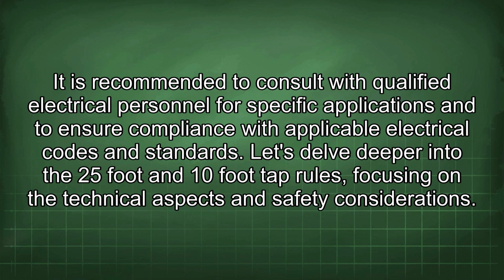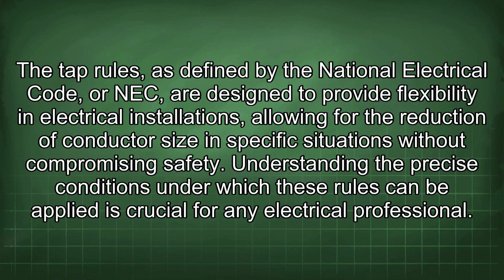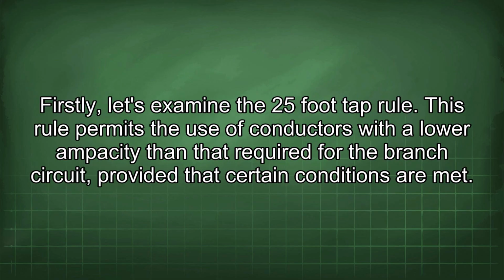Let's delve deeper into the 25-foot and 10-foot tap rules, focusing on the technical aspects and safety considerations. The tap rules, as defined by the National Electrical Code, or NEC, are designed to provide flexibility in electrical installations, allowing for the reduction of conductor size in specific situations without compromising safety. Understanding the precise conditions under which these rules can be applied is crucial for any electrical professional. Firstly, let's examine the 25-foot tap rule.